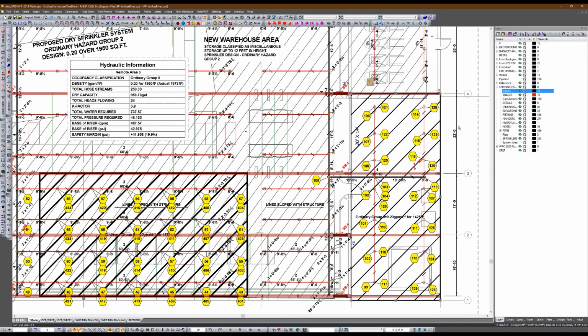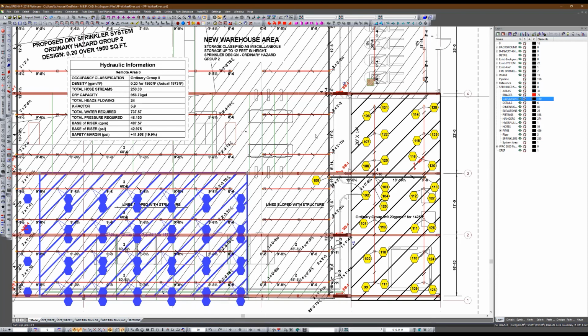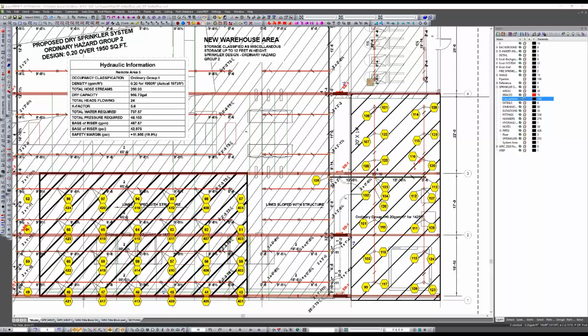Okay, that's much better. So you probably will end up having to go through and renumber your node tags for each remote area after turning off the dynamically renumber. But once you do that, those numbers should no longer change. That dynamic renumber, like I said, leads to a lot of trouble. So with that off, you should be in good shape at this point. So go through, renumber some node tags, verify things aren't changing, and you can stay on the line. I'm going to jump to the next person here, and we'll circle back to you a little later, okay? Okay, thank you. You got it.